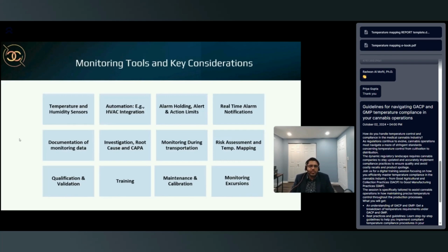One interesting thing in growing cannabis is you have to apply a lot of water. Like any crop, you have to apply a lot of water. So when you apply a lot of water, either in the form of fertigation or you're applying pesticides, what it does is, if you have a humidity set, for instance, at 60%, let's take the number 60%, when you apply those fertilizers or pesticides, humidity is going to spike. It's going to spike to 80% or 90%. Now, if that 80% or 90% excursion is happening, you're going to get so many false alarms that it will, in my terminology, blow up your mind. Like, you will have so many false alarms. Either you have to shut it off or you don't want to receive those false alarms.